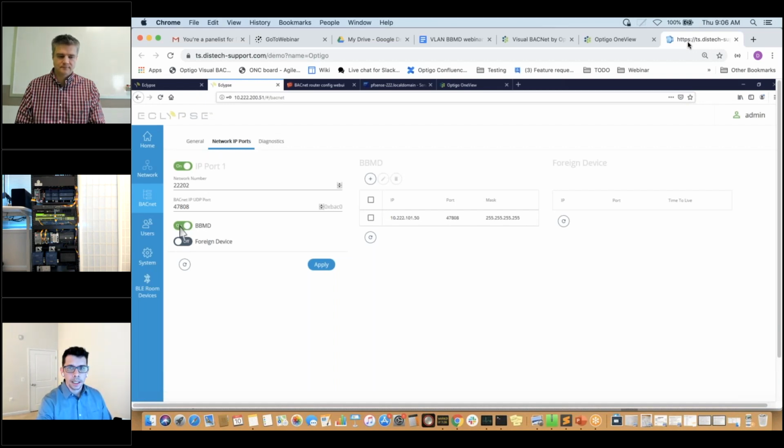When you enable BBMD, and let's say I didn't have an entry here, if I enable BBMD, that basically means I'm accepting that traffic. If somebody sends traffic to me, I'm going to rebroadcast it to my network. That's what that means. So as soon as I turn that on, I'm a client, waiting for traffic to come. That's fine. It's just sitting there waiting. If nobody sends it traffic, it's not going to do anything. So having that enabled right now, if nobody's sending me traffic, it won't do a thing. But when it's on and somebody directs traffic towards me, then I'm going to get it.